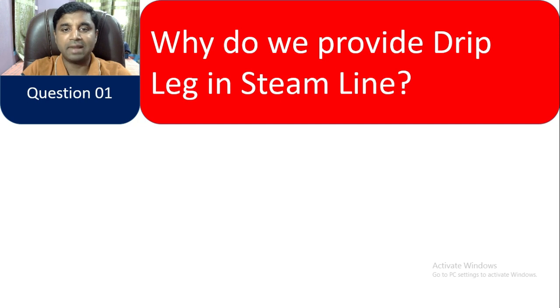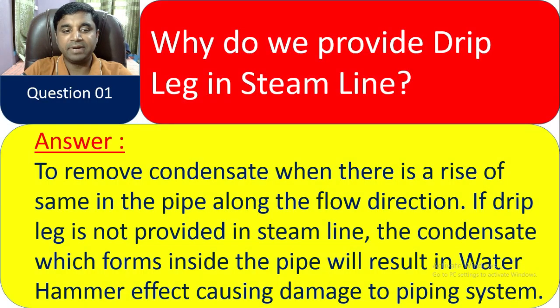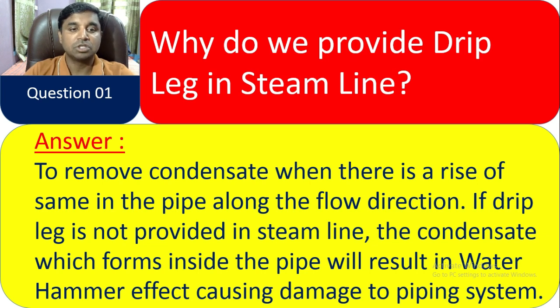Question 1: Why do you provide a drip leg in a steam line? The answer is to remove condensate when there is a rise in the pipe along the flow direction. If a drip leg is not provided in the steam line, the condensate which forms inside the pipe will result in a water hammer effect, causing damage to the piping system.